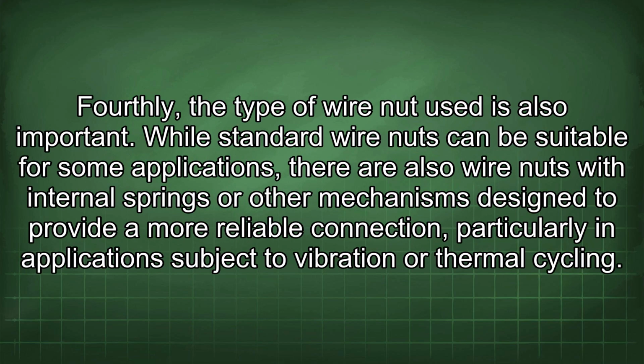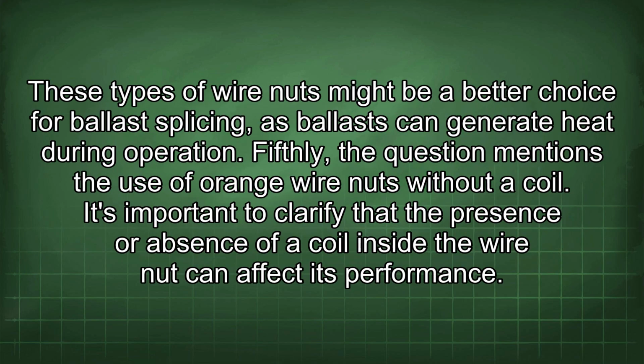Fourthly, the type of wire nut used is also important. While standard wire nuts can be suitable for some applications, there are also wire nuts with internal springs or other mechanisms designed to provide a more reliable connection, particularly in applications subject to vibration or thermal cycling. These types of wire nuts might be a better choice for ballast splicing, as ballasts can generate heat during operation.